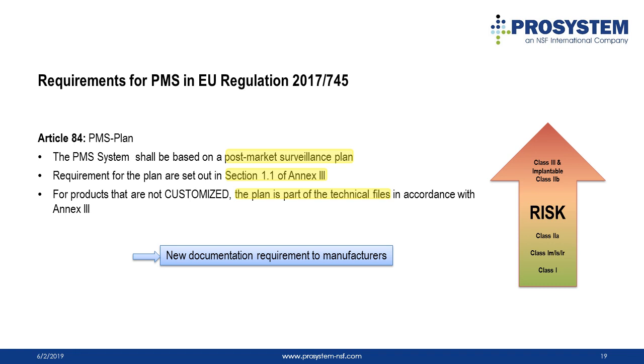But certainly, a manufacturer of a Class 1 device is not expected to perform the same extent and frequency of post-market clinical follow-ups as the Class 3 devices. For your Class 1 device, your notified body may accept studies that are simpler in design, therefore reducing the threshold for the patient to participate and reducing the associated costs to complete the investigation.